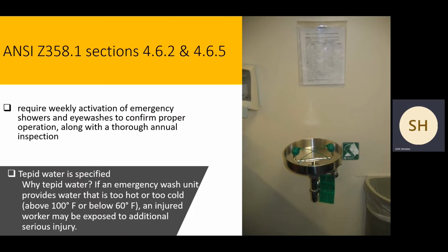We have many places that say, when I ask, do you check it for tepid water? They say yes, and I say how? And they say, well, I stick my fingers in there, and if it's lukewarm, not too hot, not too cold, that's tepid. If OSHA didn't give a definition with a specific range, then this could probably work. But I have to say to you, your fingers can tolerate things that your face and eyes could not. So something that does not feel too hot or too cold to your hand might feel extremely hot or extremely cold to your face, for one. For two, if something were at 55 degrees, could your fingers tell if it was 55 degrees and not 60? I kind of doubt it.